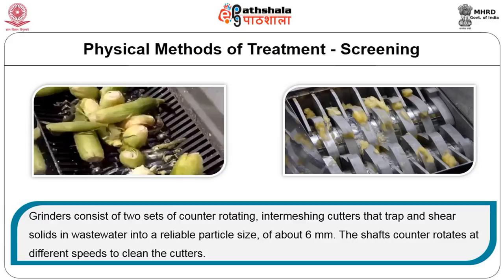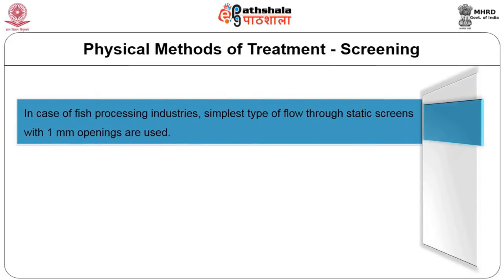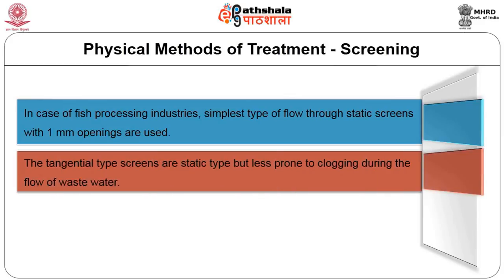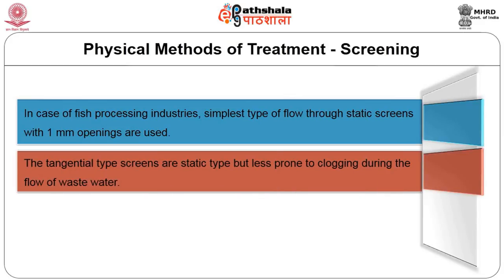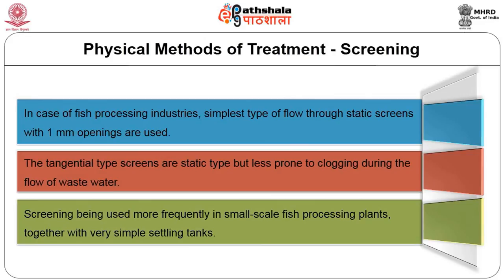The shafts counter-rotate at different speeds to clean the cutters. In fish processing industries, the simplest type of flow-through static screens with 1 mm openings are used. Tangential type screens are static but less prone to clogging due to the flow of wastewater. Screening is used more frequently in small-scale fish processing plants together with very simple settling tanks. The next method is sedimentation.